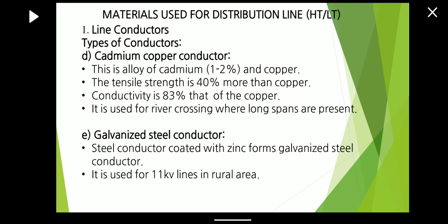The next type of conductor is the cadmium copper conductor. This is an alloy of copper and cadmium, with cadmium inserted at 1 to 2%. The tensile strength is 40% more than copper, and conductivity is 83% that of copper. It is used for river crossings where long spans are present, and also for telegraph and telephone lines.